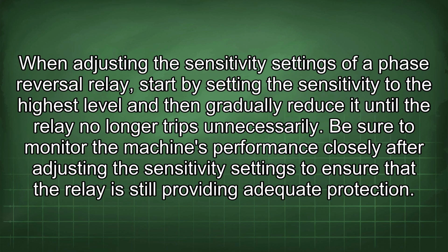When adjusting the sensitivity settings of a phase reversal relay, start by setting the sensitivity to the highest level and then gradually reduce it until the relay no longer trips unnecessarily. Be sure to monitor the machine's performance closely after adjusting the sensitivity settings to ensure that the relay is still providing adequate protection.